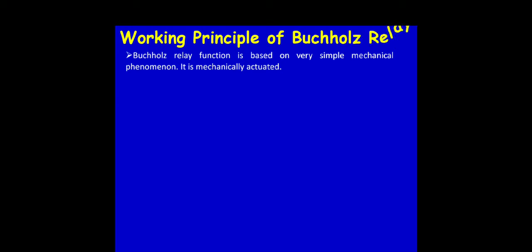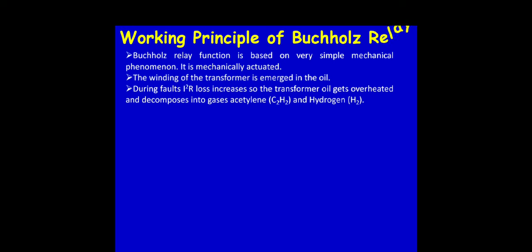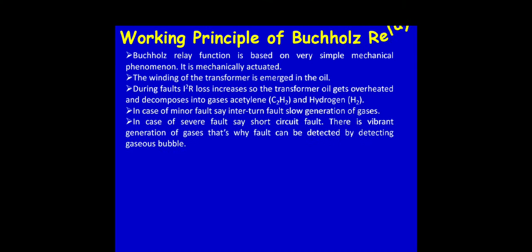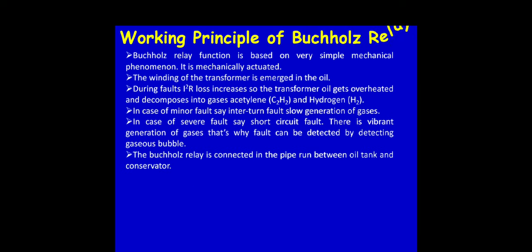The working principle of the Buchholz relay is based on a simple mechanical phenomenon; it is mechanically actuated. The winding of the transformer is immersed in oil. During faults, I-squared-R losses increase, the transformer oil gets overheated and decomposes into gases — acetylene (C₂H₂) and hydrogen (H₂). In case of a minor fault, there is slow generation of gases, but in case of a severe fault such as a short circuit, there is a rapid generation of gases. Faults can be detected by detecting these gaseous bubbles.